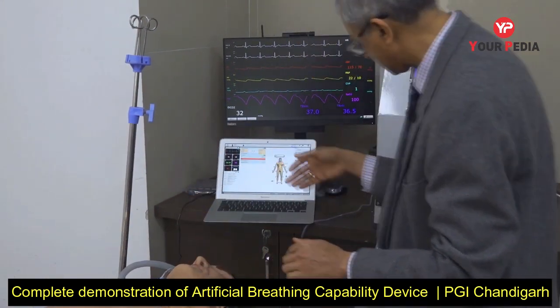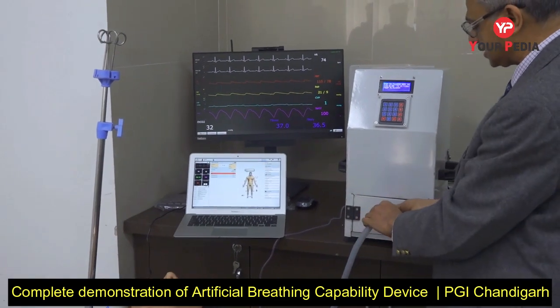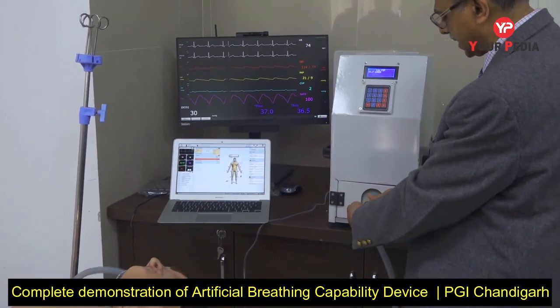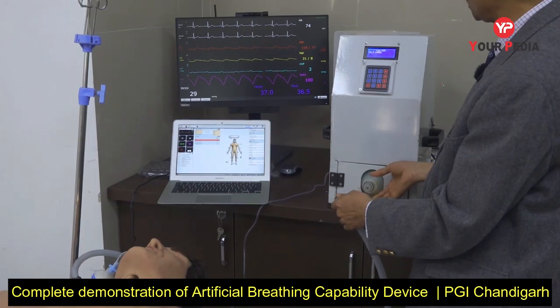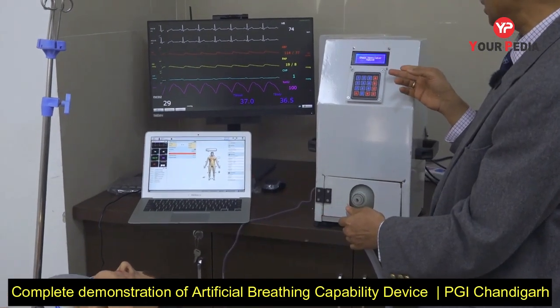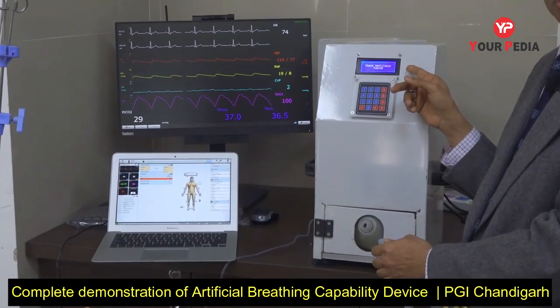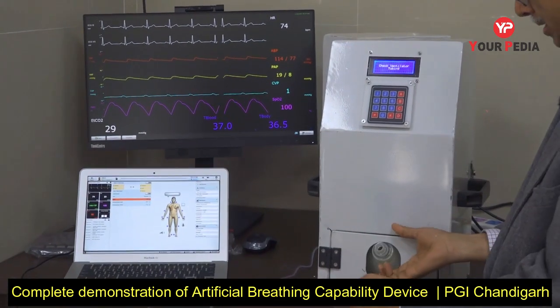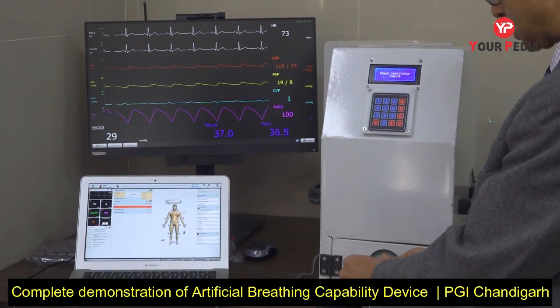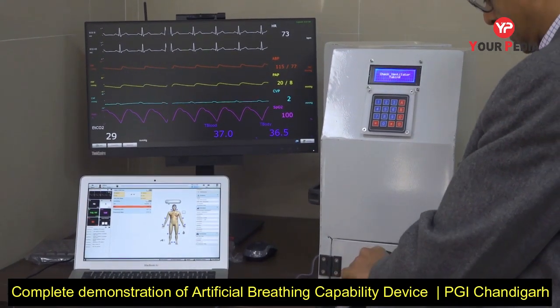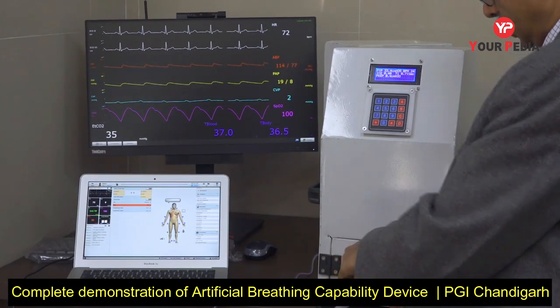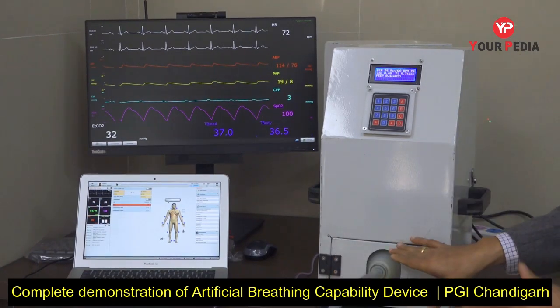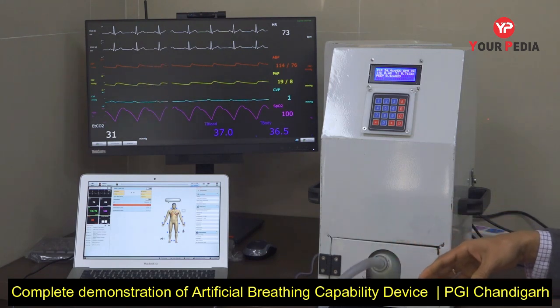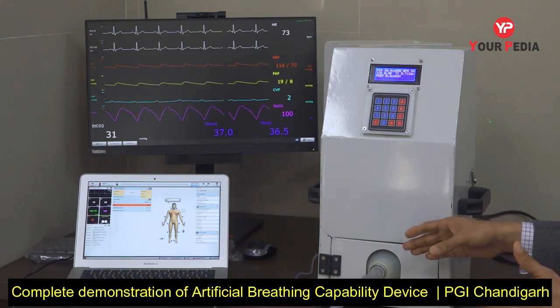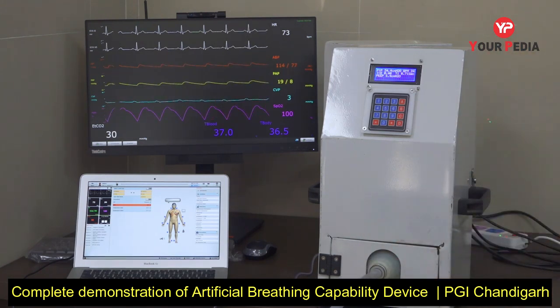We also have mechanisms in case the tubing of the ventilator gets disconnected like this. You see that there is not enough pressure which is generated. Immediately an alarm goes on the screen to check the ventilator tubing. So this is a safety mechanism which has been built in over here. In the same way we have an alarm if this self-inflating bag gets displaced or it is not in the right position, there is an alarm on the screen which comes up.